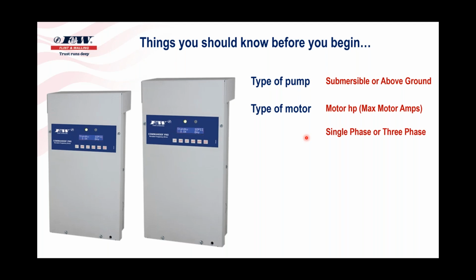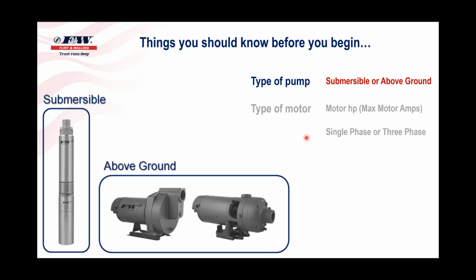We also want to know if it's a single phase or a 3-phase motor. And again, just having this knowledge in our head as we go up to the drive to program it is going to make all our programming extremely simple and easy. Like I said, some of this is a little fundamental and some of it's going to require a little more moxie. So for example, type of submersible pump. What we're looking at are the motors or type of pump, submersible or above ground. Again, this is not to insult intelligence. There are some seasoned people out there, but if you're brand new to this, that's what we're talking about.